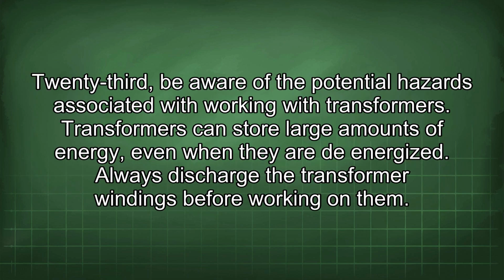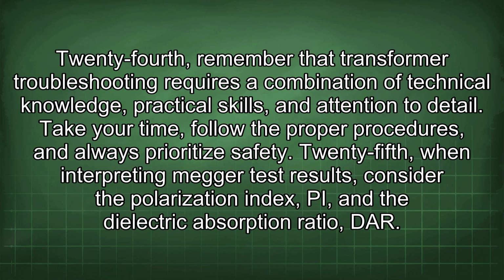23rd, be aware of the potential hazards associated with working with transformers. Transformers can store large amounts of energy, even when they are de-energized. Always discharge the transformer windings before working on them. 24th, remember that transformer troubleshooting requires a combination of technical knowledge, practical skills, and attention to detail. Take your time, follow the proper procedures, and always prioritize safety.